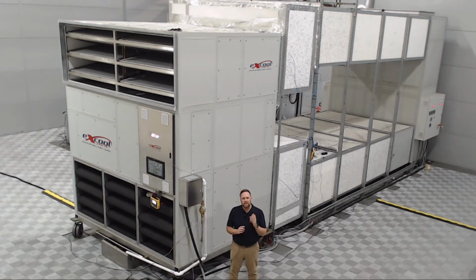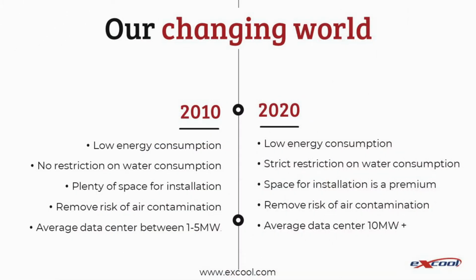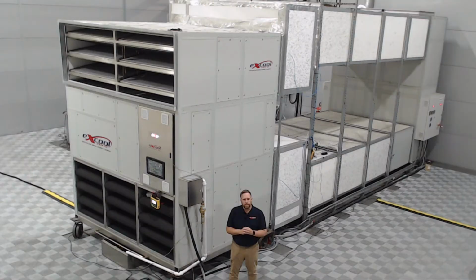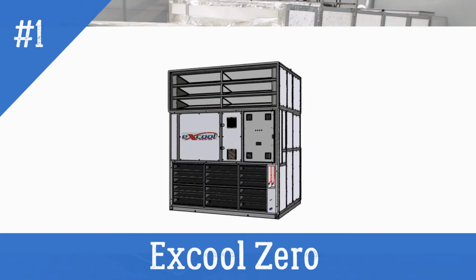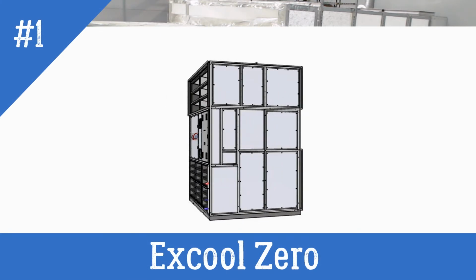It addresses the challenge that did not exist 10 years ago. Data centre developments are far larger today than they were a decade ago. We cannot continue to use a valuable resource such as water at the same volume as we did back then. Excool Zero addresses this and has lowered our dependency on water to a point where we can operate the system with minimal water quantities and even run dry if required or even when water is unavailable.